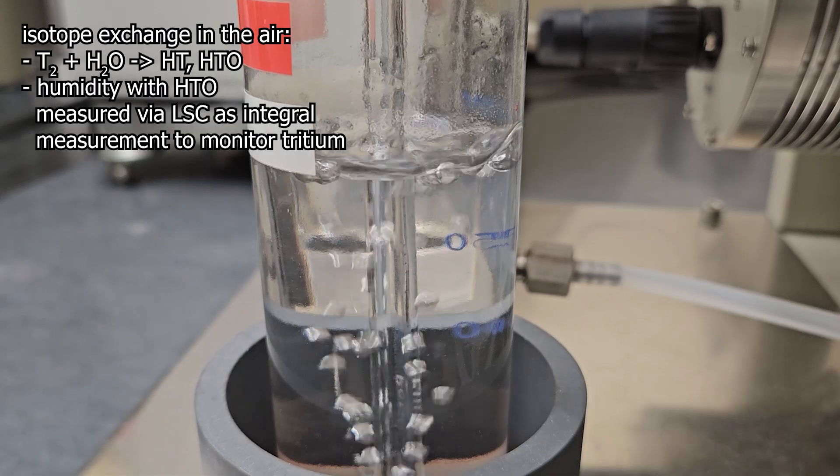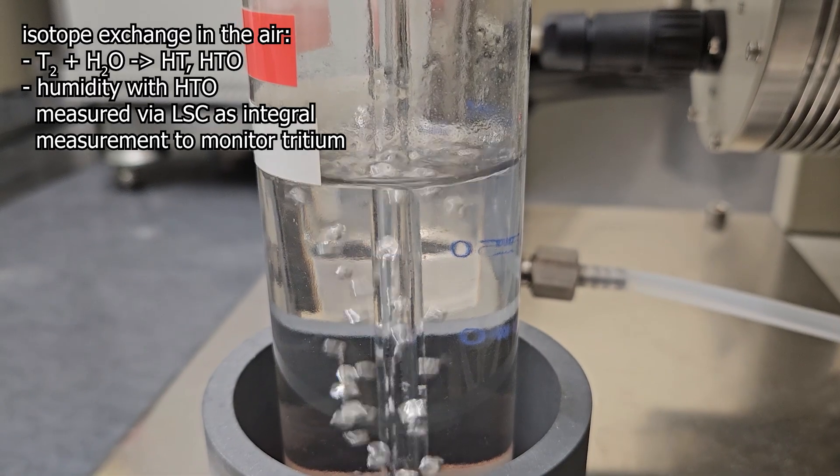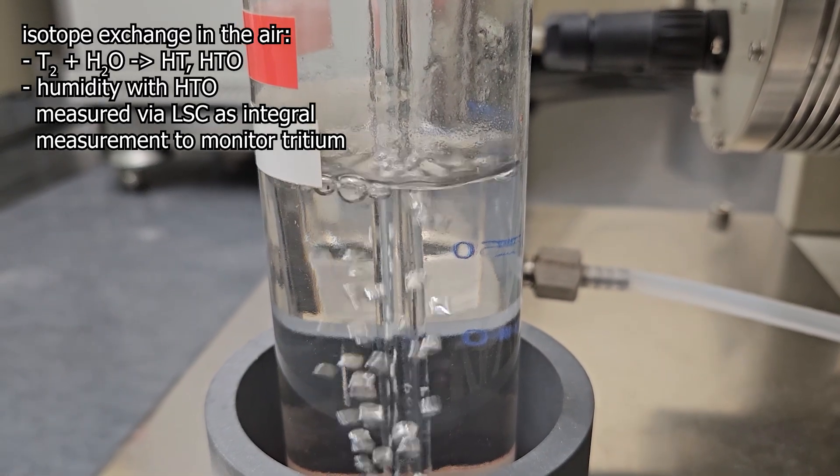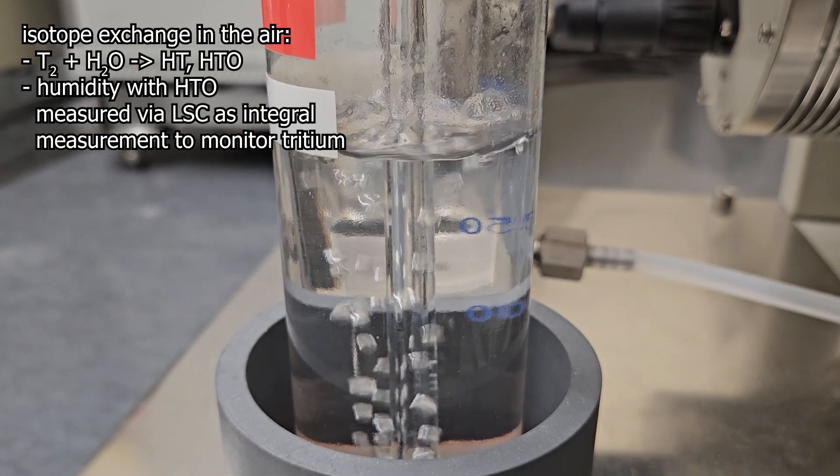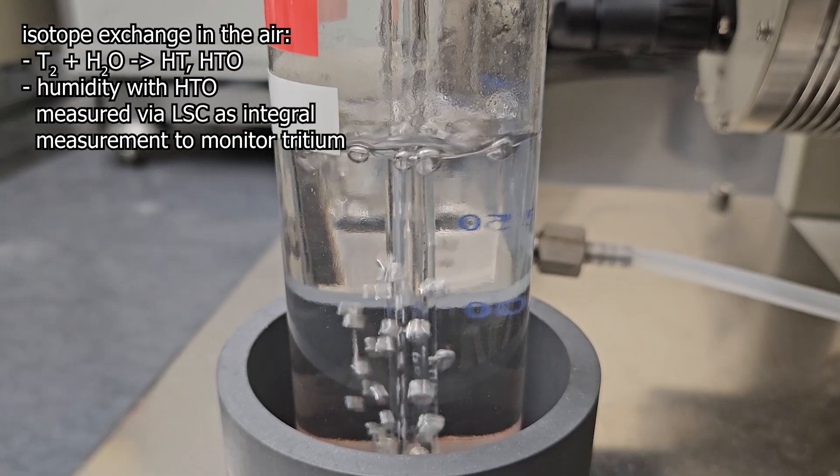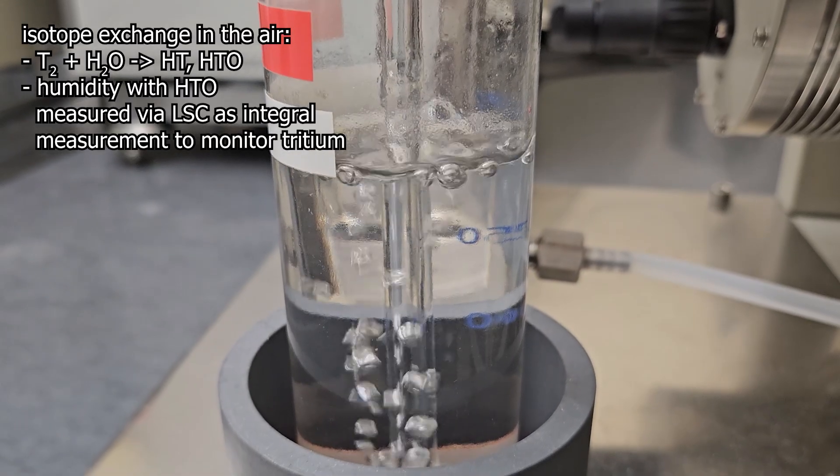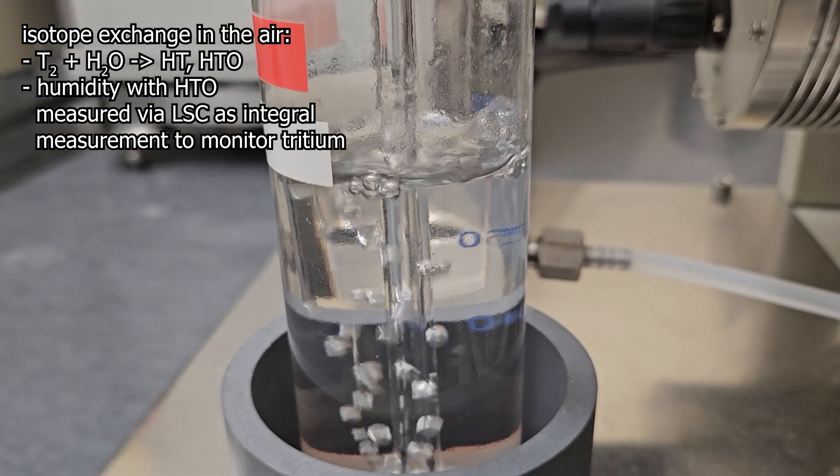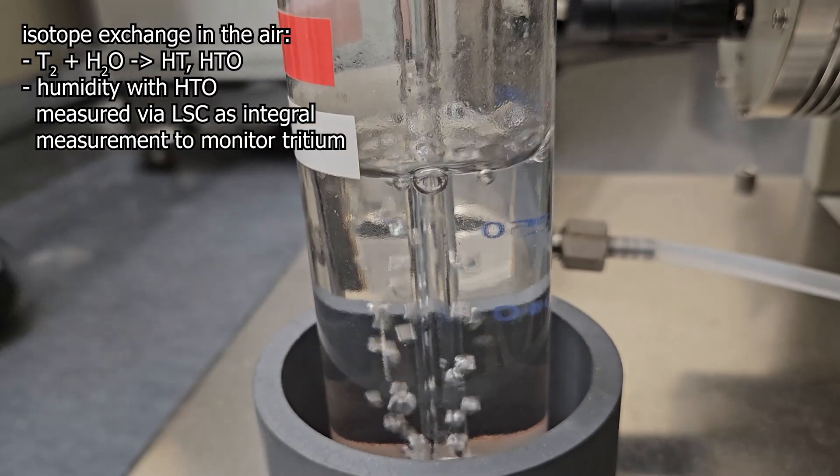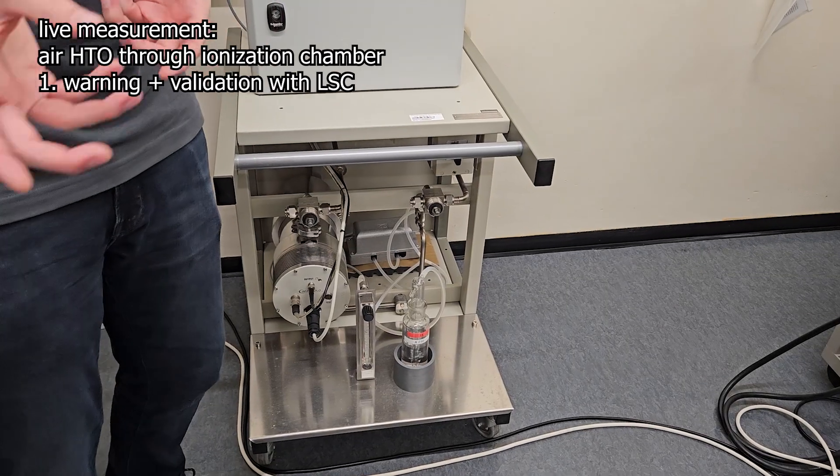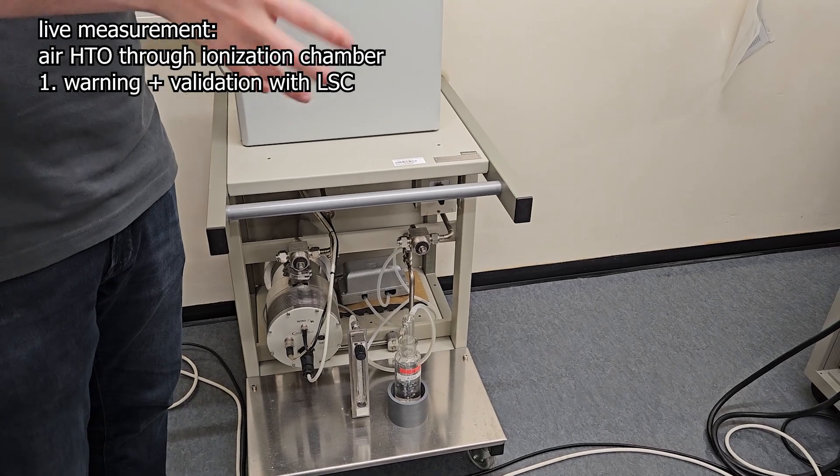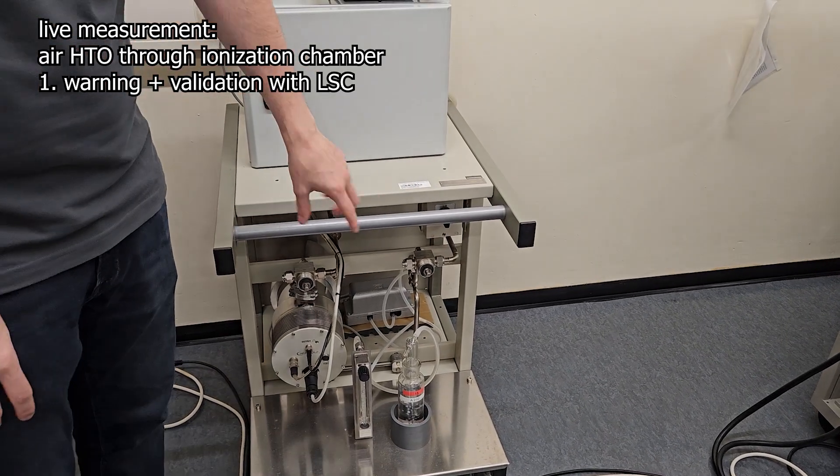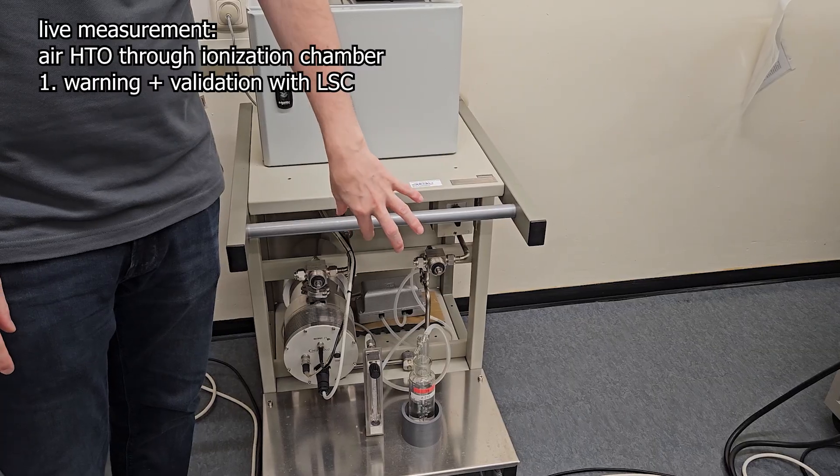Water containing tritium is important for exposure monitoring, because unlike the classical gaseous tritium compound, it has a very high bioavailability and therefore has a higher dose factor. It must be therefore monitored more closely, hence the most sensitive measurement via LSC. So if tritium gas were to escape somewhere, it could be measured by the live measurement at the ionization chamber and would later be confirmed again in the LSC measurement of the water.